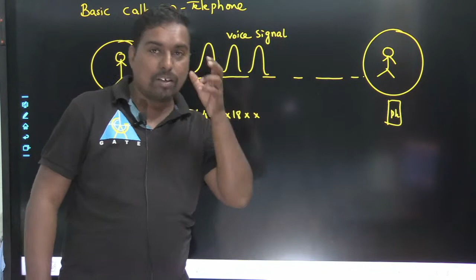So just like a voice signal and caller ID are superimposed, that technology they wanted to introduce into our instrumentation. Because if I am using 4 to 20 milliamperes, we know that is analog data communication, isn't it? Yes, pressure signal or temperature signal is adjusted to 4 to 20 milliamperes.